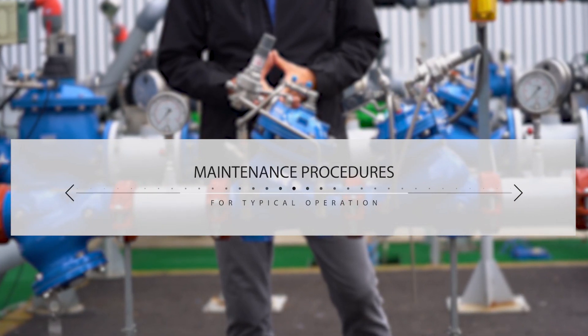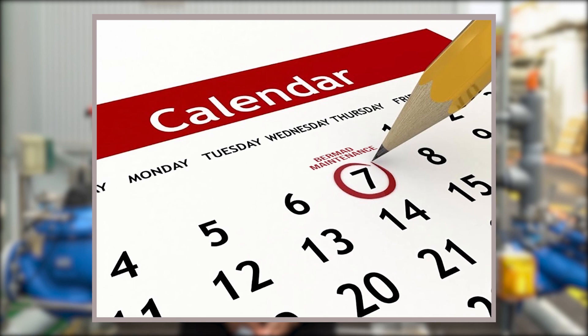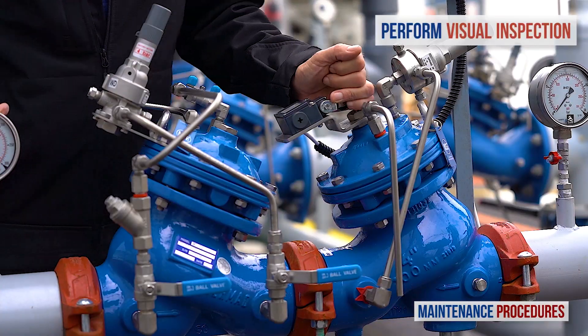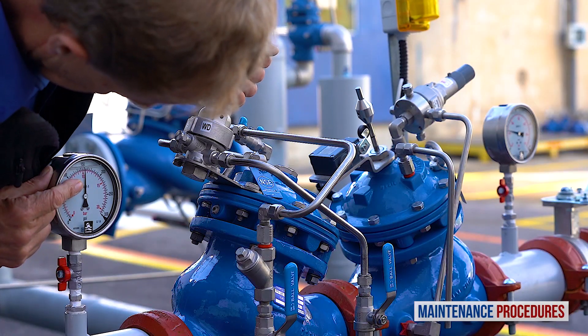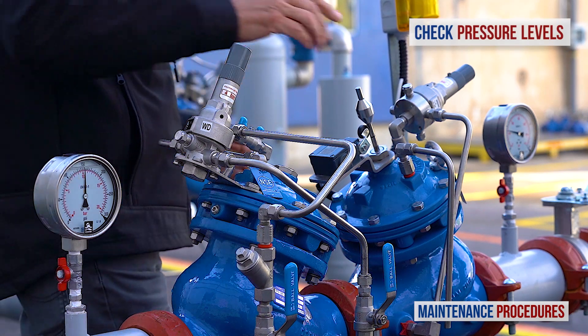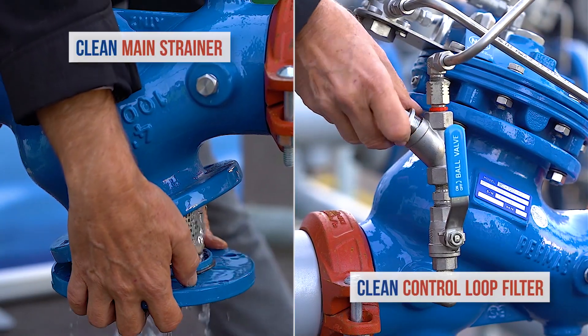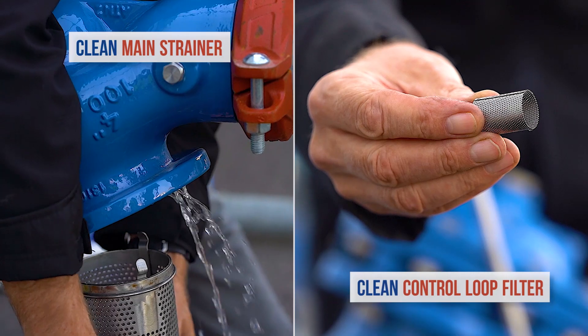Now let's discuss maintenance procedures for the Bermad pressure-reducing station with shut-off valve. Note that your schedule for preventative maintenance depends on actual conditions of use and the station's environment. On a weekly basis, perform a visual inspection of the station and check for leaks and external damage. Also observe the unit's pressure gauges to make sure that the pressures upstream and downstream are as they should be. Once a year, close both the upstream and downstream isolation valves and clean the main strainer and the valve control loop filter. Every three to five years, inspect the internal condition of the pressure-reducing valve.